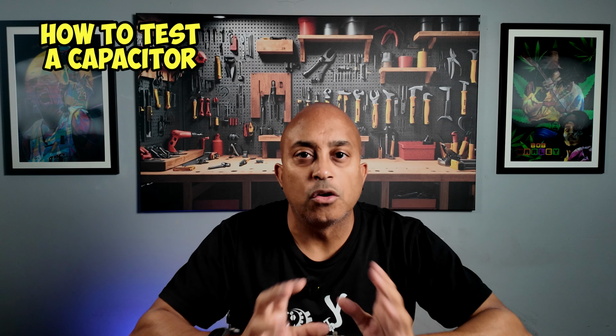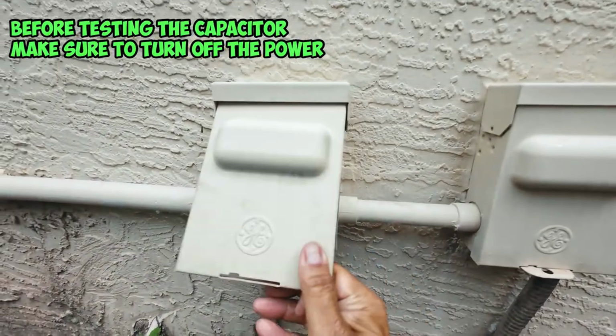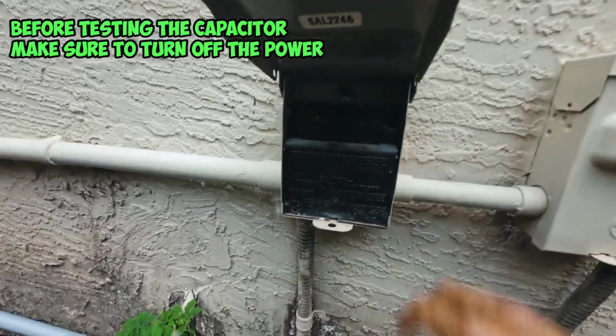So now, once you know that your contactor is good and you want to go ahead and test your capacitor, the first thing you want to do is go over to your breaker or your disconnect box and turn off the power that's going to your outdoor unit. This is very important, you guys, you don't want to be messing around with high voltage and getting shocked. Just take the necessary precautions, turn off the power, and then we can go ahead and get to troubleshooting.